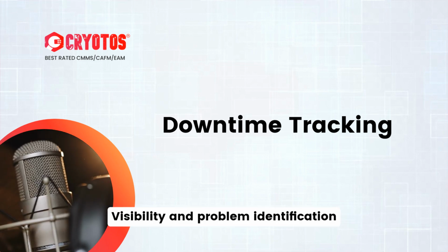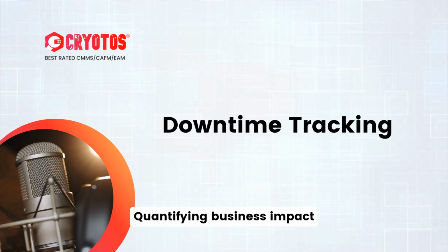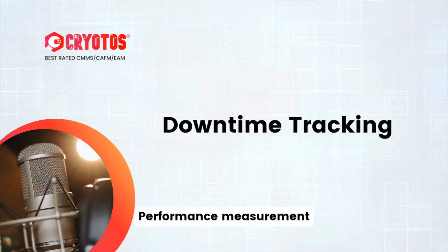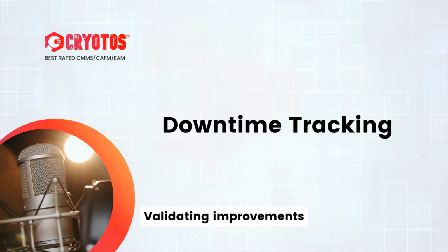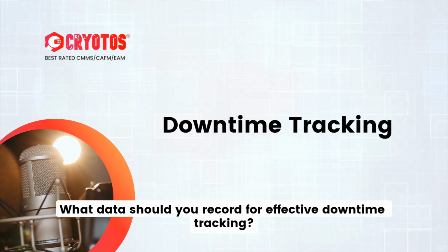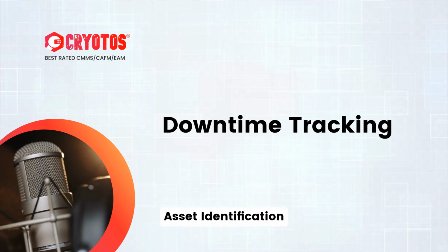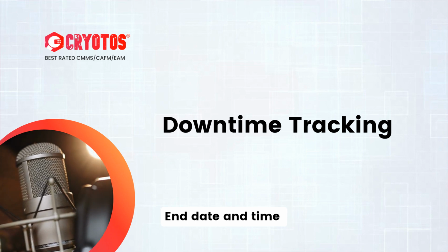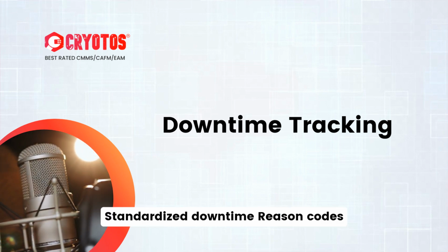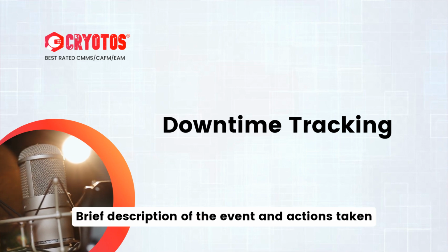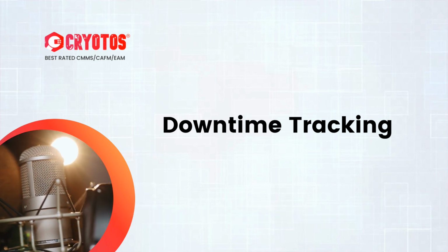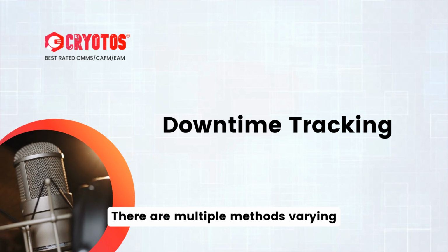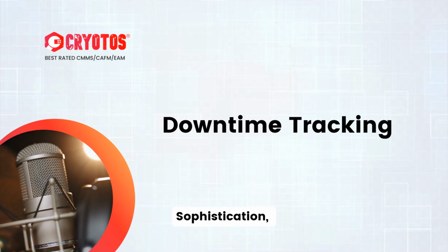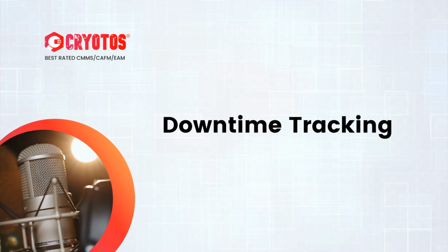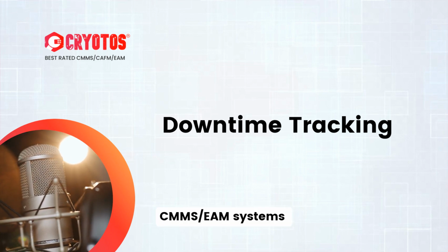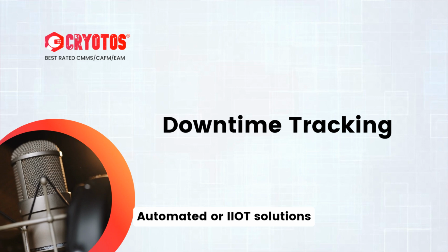Visibility and problem identification, quantifying business impact, root cause analysis, performance measurement, validating improvements. What data should you record for effective downtime tracking? Asset identification, start date and time, end date and time, total duration, standardized downtime reason codes, brief description of the event and actions taken. How do you capture this information? There are multiple methods, varying in sophistication: manual logs, CMMS, EAM systems, automated or IIoT solutions.